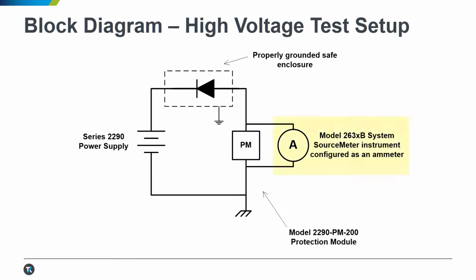Our source meter is in series with the DUT and will be used as a sensitive ammeter to measure current through the DUT. The protection module is in parallel with the source meter to provide a fast responding short circuit to prevent damage from the high voltage that could be applied to the source meter should the DUT break down. The protection module senses when the voltage across itself and the source meter exceeds 200 volts, the maximum safe voltage for the source meter. The protection module turns on and protects the source meter from high voltage damage.